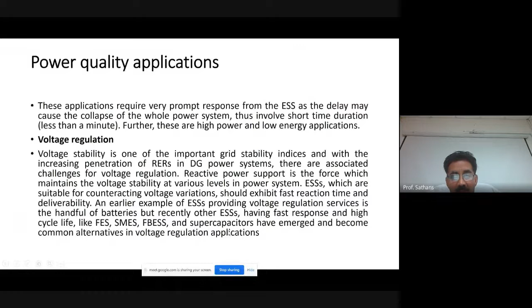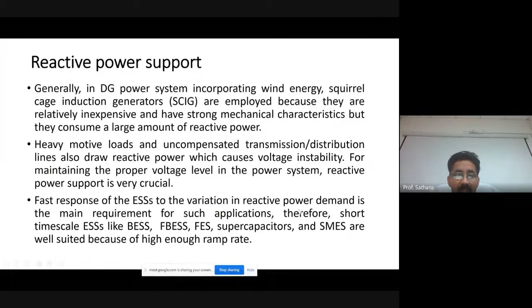You obviously need the reactive power support to come through the energy storage systems. And these are some of the energy storage systems that have pretty fast response time, for example SMES, FES, flow batteries, supercapacitors even. Reactive power support is needed in DG power systems, especially in wind, squirrel cage induction generators, and they do consume a lot of reactive power, and as a result, the requirement. And there are some other kinds of loads also, wherein reactive power support is very, very important.